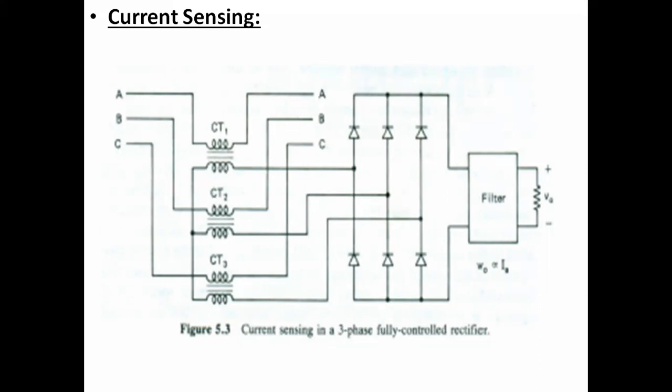Right? So if you want to use any speed drive, we first have to ensure accurate sensing of current, and the drop across the interpole winding is used for current sensing. The isolation transformer is used in the following circuits. The voltage drop across the shunt is filtered, amplified, modulated, and then applied to the primary of the isolation transformer.